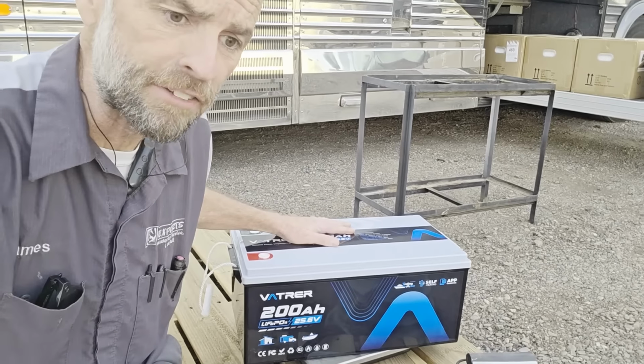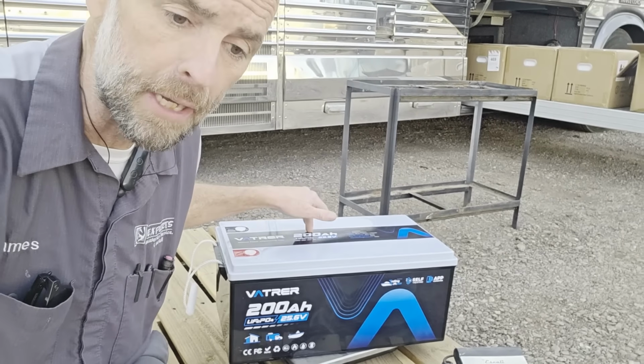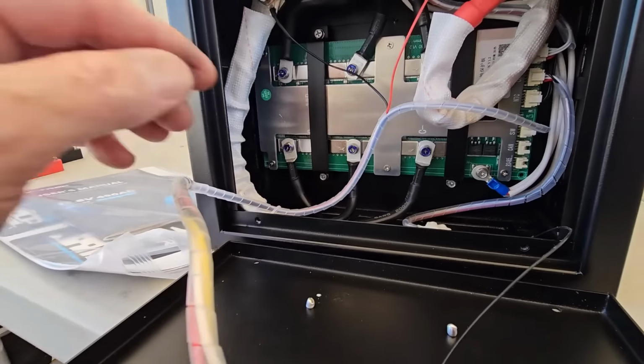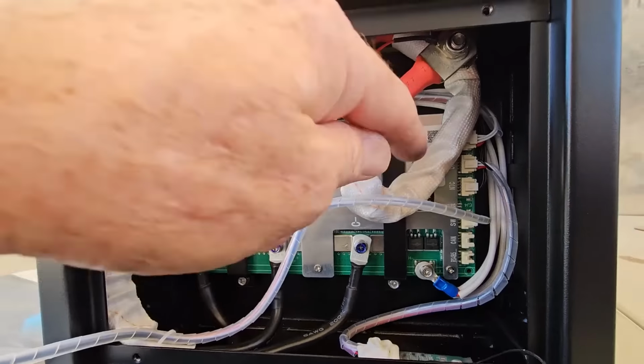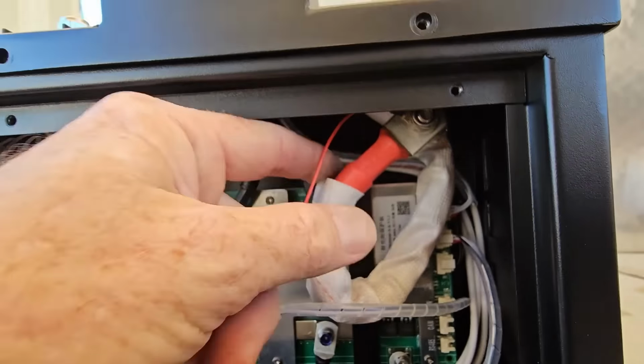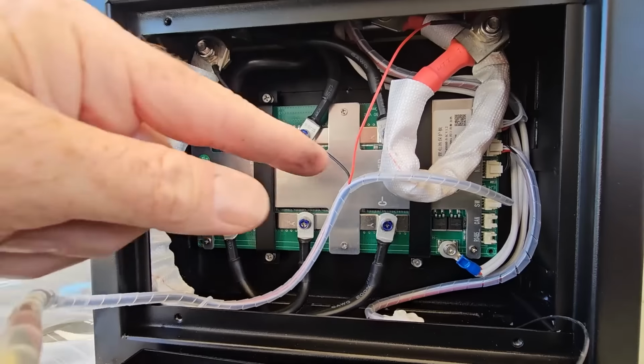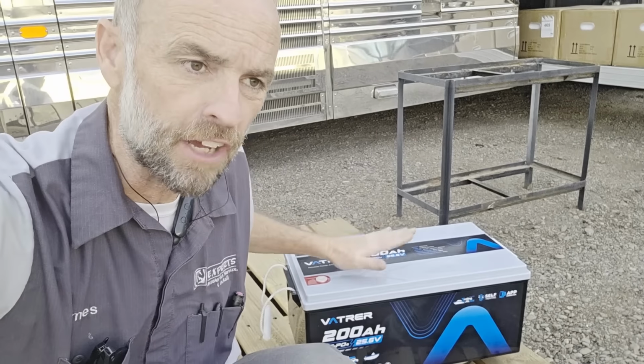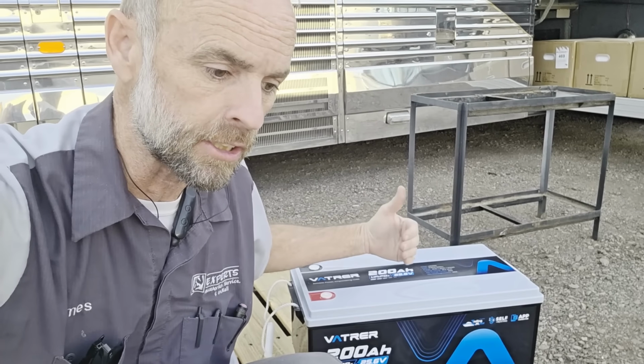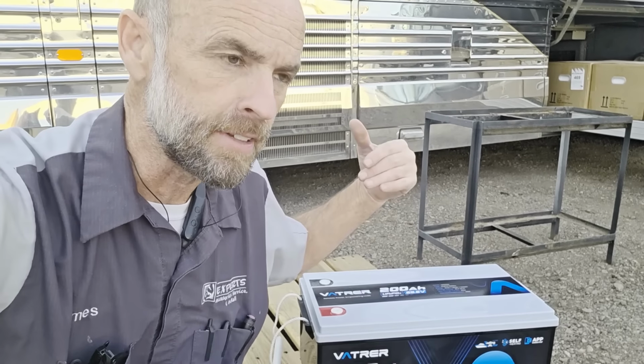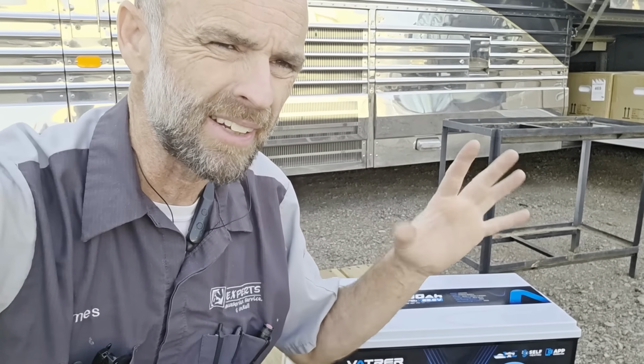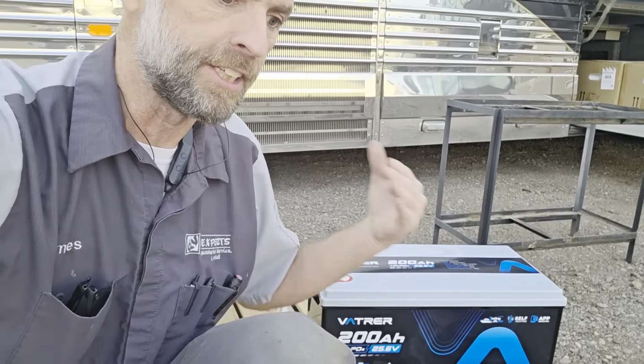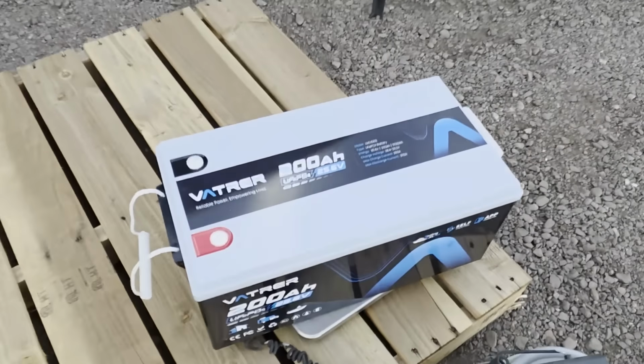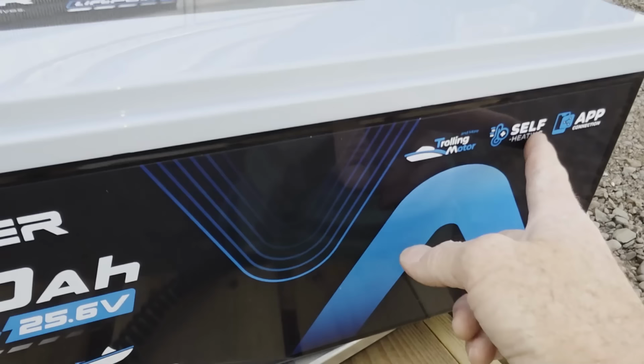Most modern lithium iron phosphate batteries, like this one right here, do have a smart BMS built into them, which is a smart microprocessor on a board that is connected to each individual one of the cells to keep all the cells in voltage balance. And if the battery starts to get too cold, which means at 0 degrees Celsius or 32 degrees Fahrenheit, the BMS shuts off charging, so it won't try to charge the battery at that temperature. If it gets colder, I think negative 20 degrees Celsius, which is about negative 5 degrees Fahrenheit, it will shut off discharging too. But just like the last Vatrer battery I installed, this does have self-heating on it.